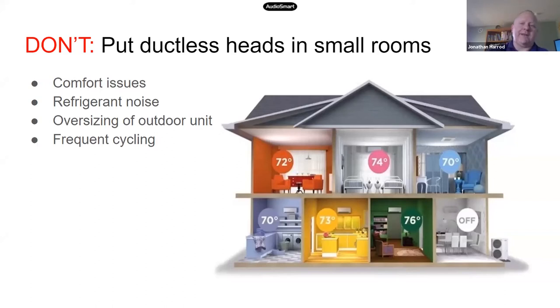So what can happen is that you have to install an outdoor unit that is pretty close to the sum of all the indoor units. If each of your indoor units is twice as big as it really needs to be for that room, you end up with an outdoor unit that's also twice as big and isn't able to modulate down far enough that when only one or two rooms is calling for heat, it's able to run and run efficiently. And so this can lead to all kinds of problems.